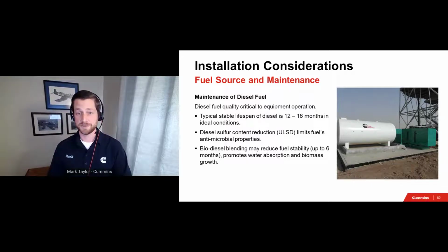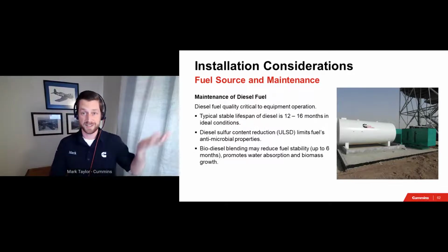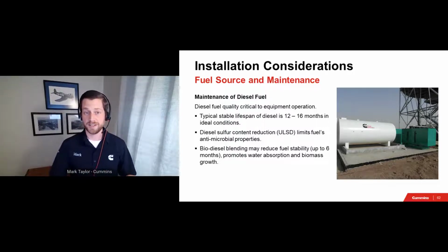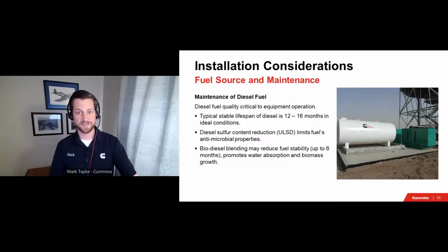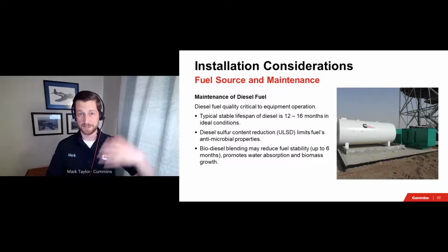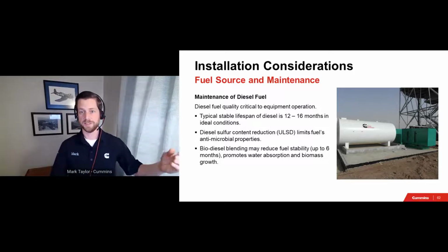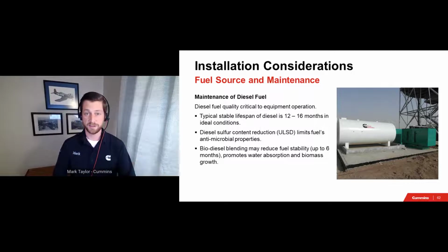First and most obvious is that diesel drives the need to store and maintain fuel on site, right? As we mentioned earlier, code requirements will drive the NFPA 110 class, which in turn drives the size of the on-site storage. The more fuel that is present, the more fuel that needs to be maintained. Fuel does not stay perfect forever. Above ground tanks are open to the atmosphere and they need to breathe. A breathable tank not only allows for filling and fuel consumption, but also the accommodation of seasonal and daily temperature fluctuations.